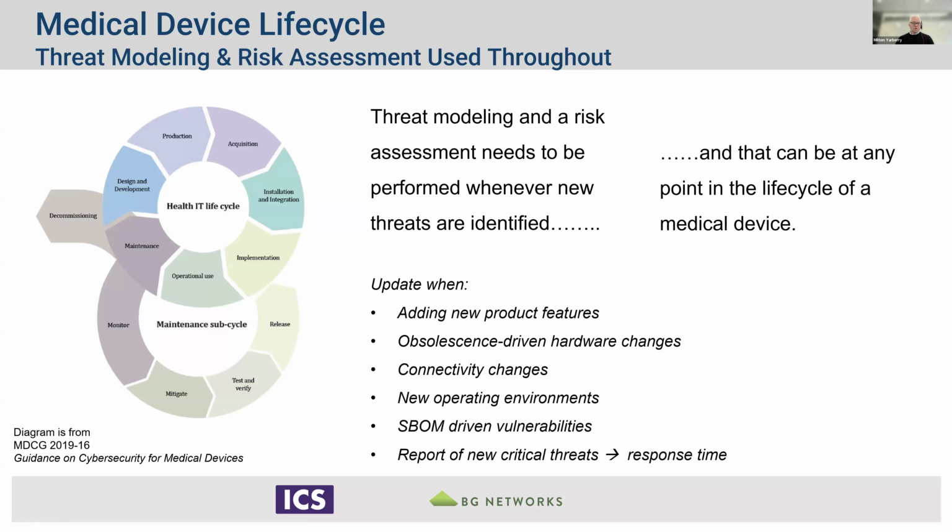And so this can also be after the product has gone to market. You should think of updating these too when you have new product features, since they might change your attack surface and therefore require updating these assets. But also obsolescence-driven hardware changes, where you have a piece of hardware that you can't get anymore and you're replacing it, it's going to have a whole new cybersecurity profile. Of course, connectivity changes. If you didn't have a network connection and now you do, or you have a different type of connection, or that connection goes through different levels of security boundaries.